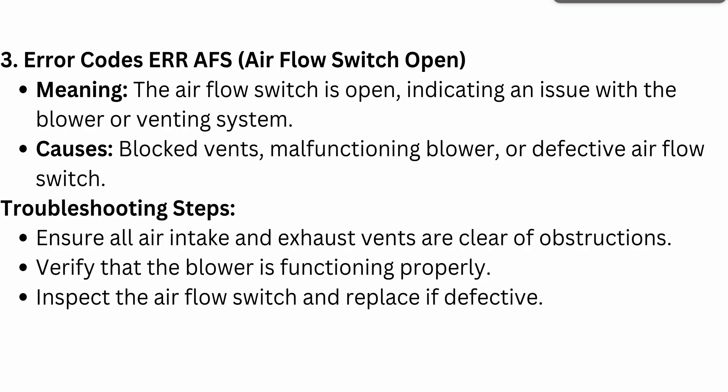The next error code is ERR AFS — air flow switch open. It means the air flow switch is open, indicating an issue with the blower or venting system. The causes may be blocked vents, a malfunctioning blower, or a defective airflow switch. To troubleshoot, ensure all air intake and exhaust vents are clear of obstructions, and verify that the blower is functioning properly.